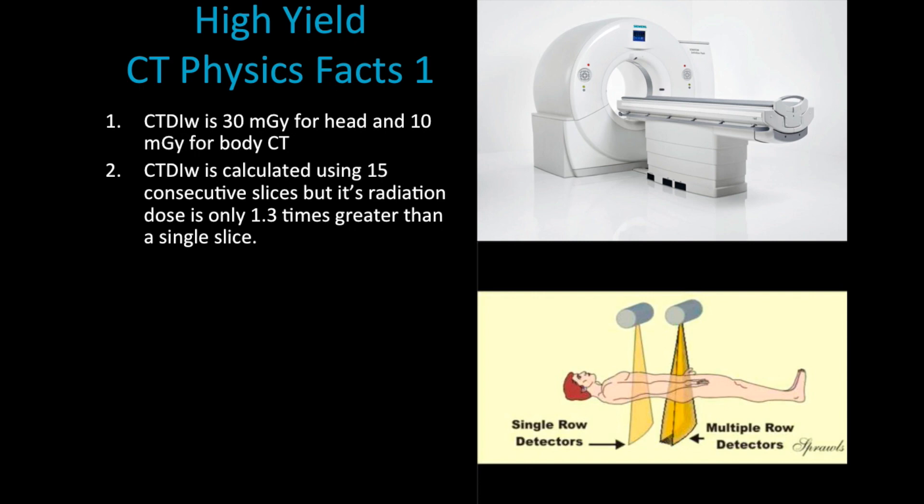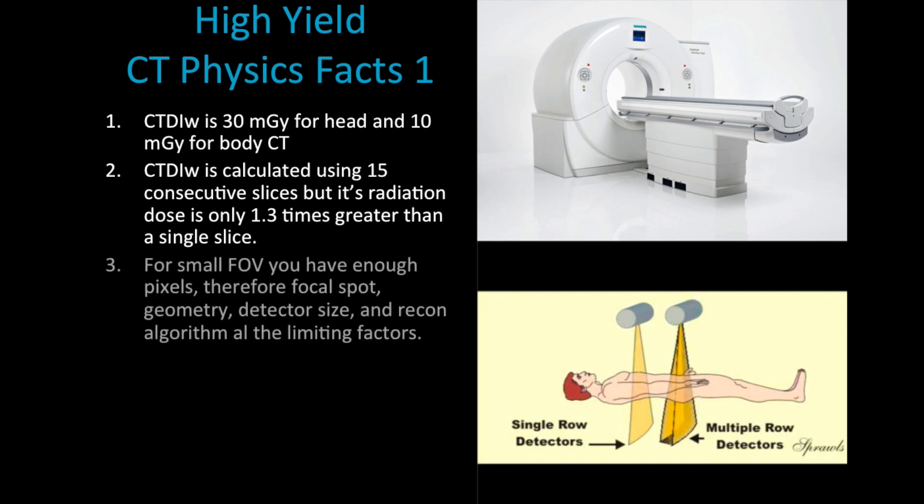Moving towards spatial resolution, a small field of view such as in a head CT has enough pixel values or pixels, and we know that's not going to be our limiting factor. Our limiting factor can be our focal spot, our geometry, or actual detector size and the different reconstruction algorithms.